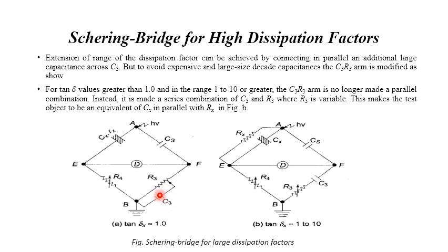So this is no longer C3 and R3 coming in parallel, but R3 is made as a slide wire along with the decade resistance, and C3 is extended by connecting a single fixed capacitor. C3 and R3: R3 is made as a slide wire, varying from a minimum to a maximum value, and C3 is extended by connecting a single fixed capacitor. Usually this modification is limited to tan delta, which is nothing but the loss angle factor, tan delta equal to 1.